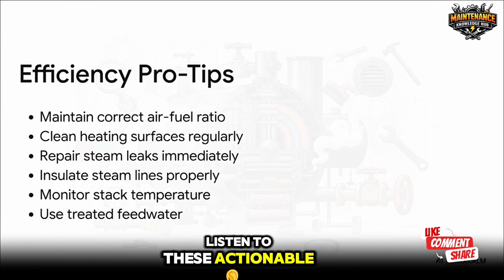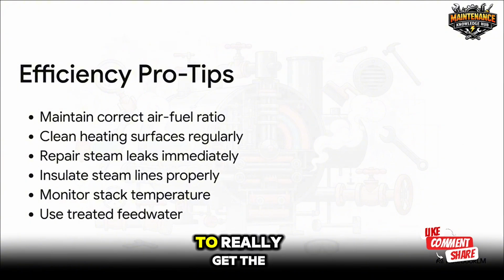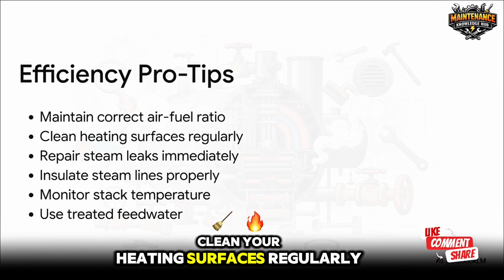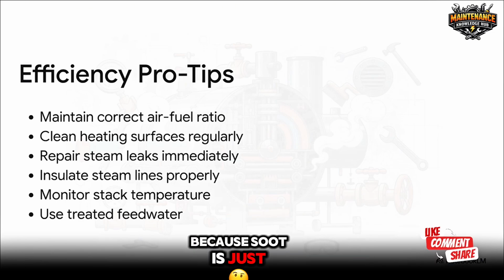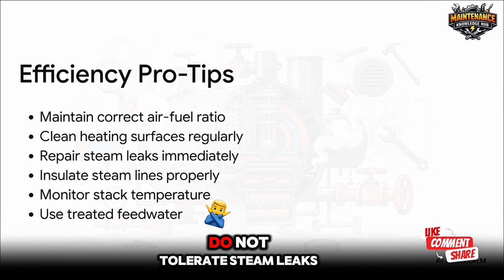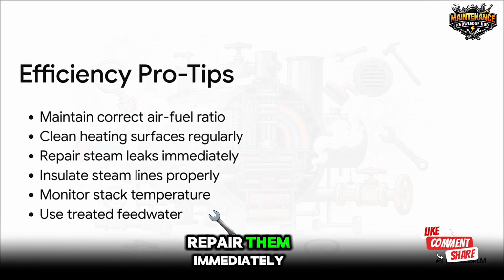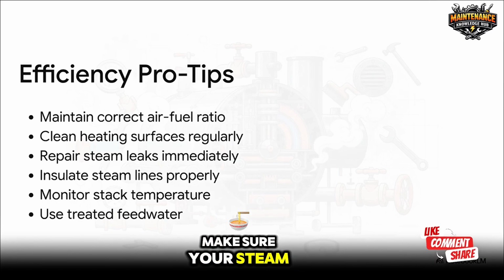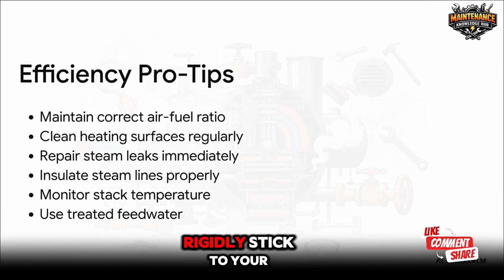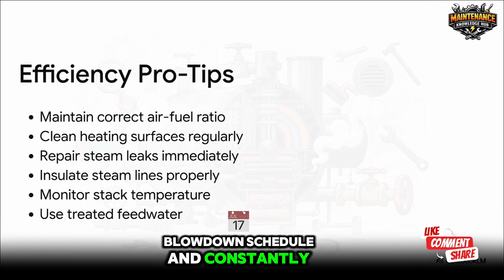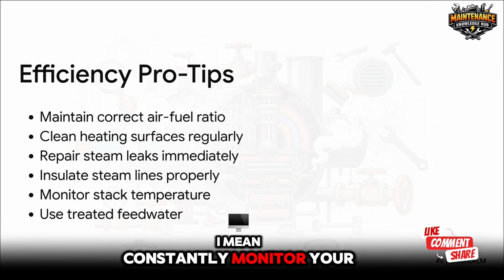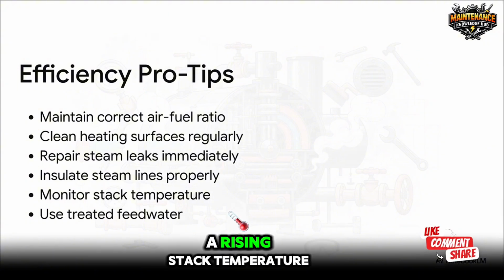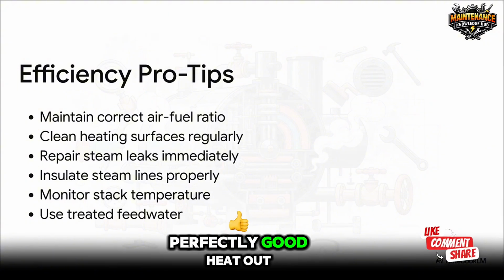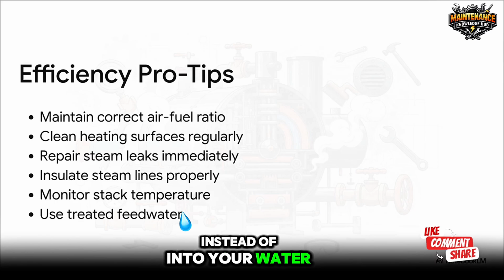Listen to these actionable pro tips from expert technicians to really get the most out of your fuel. First, strictly maintain that correct air-fuel ratio. Clean your heating surfaces regularly because soot is just a terrible conductor of heat. Do not tolerate steam leaks. Repair them immediately. Make sure your steam lines are properly insulated. Rigidly stick to your blowdown schedule. And constantly monitor your stack temperature. A rising stack temperature means you're just blowing perfectly good heat out the exhaust instead of into your water.